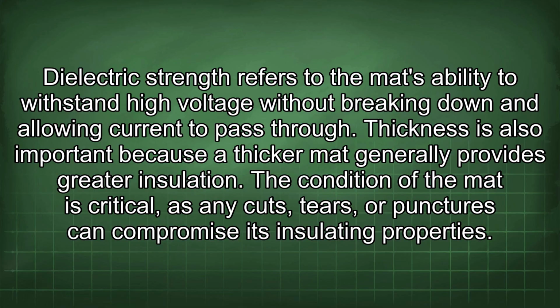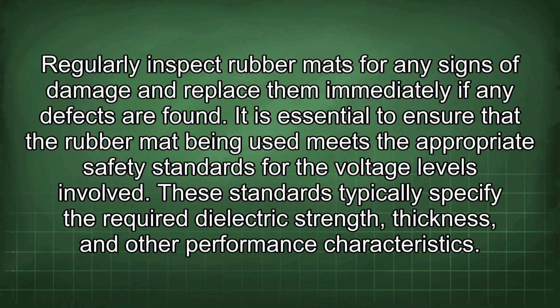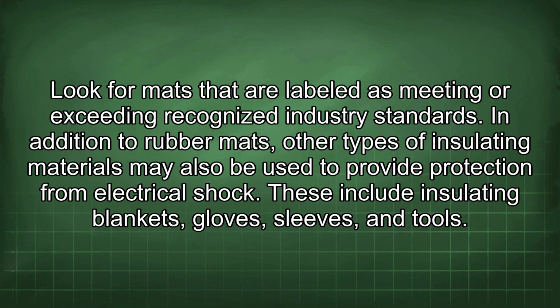Thickness is also important because a thicker mat generally provides greater insulation. The condition of the mat is critical, as any cuts, tears, or punctures can compromise its insulating properties. Regularly inspect rubber mats for any signs of damage and replace them immediately if any defects are found. It is essential to ensure that the rubber mat being used meets the appropriate safety standards for the voltage levels involved. These standards typically specify the required dielectric strength, thickness, and other performance characteristics. Look for mats that are labeled as meeting or exceeding recognized industry standards.